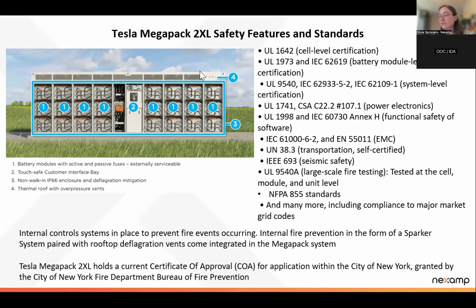The guidelines given to fire departments from the state, and also consultants who prepare these emergency response plans, are to keep a 100-foot safety boundary, to not go within 100 feet. But studies have shown that larger systems than this don't have any dangerous levels of emissions beyond 50 feet. When doing the cell level testing, like UL cell level testing, they also take air measurements, and beyond 9 feet there's not even carbon monoxide.